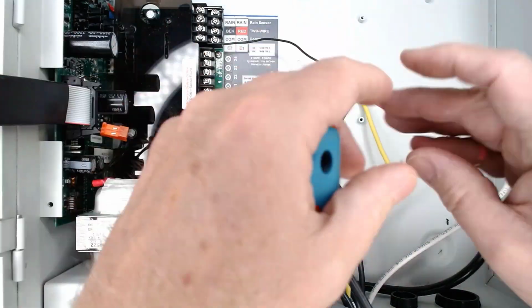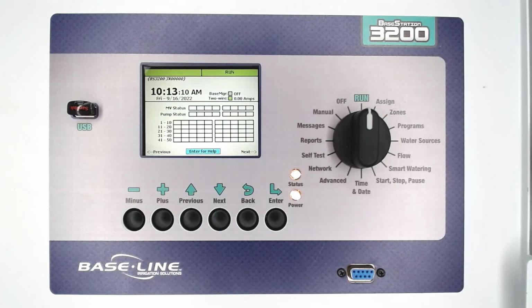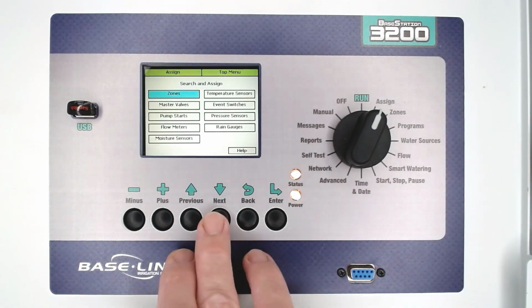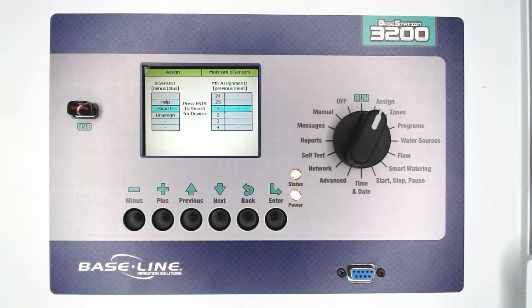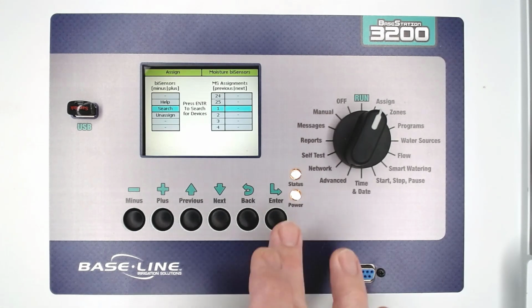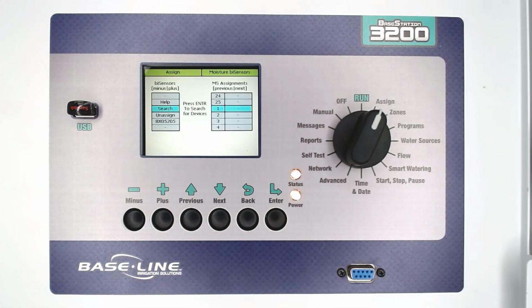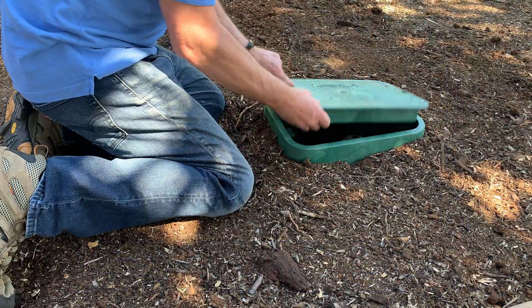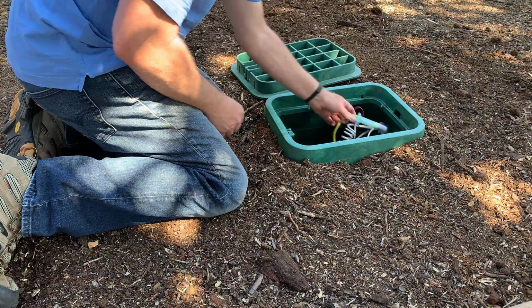I'll bring my soil moisture sensor back to the controller and connect it to a sensor-enabled terminal and the valve common. Power the controller back up and return to the assign menu looking for that same device again. If the controller can find the sensor while it's connected directly to the controller, we eliminate the device as the issue. This means the problem is either in the wire path or the splices on the wire path.